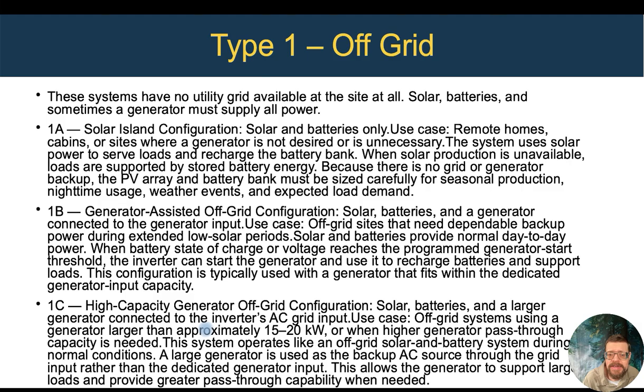Off-grid systems, that's really the simplest. We divide this into 1A, where we have no generator. A lot of people want to do no generator off-grid. I always recommend having at least a small generator, even if you don't intend on using it much, because there's always some situation where the weather is just not cooperating and you can't control your loads well enough to not use a generator. Like all the in-laws come over for Thanksgiving dinner in a big snowstorm, and you can't just turn everything in the house off to keep the batteries from going dead. You've got to keep the lights on and stuff, so having a generator is recommended.